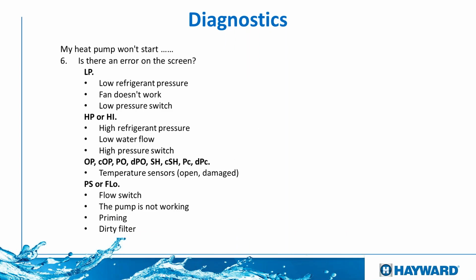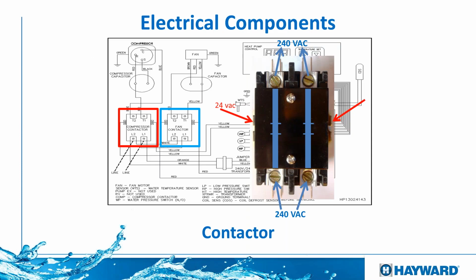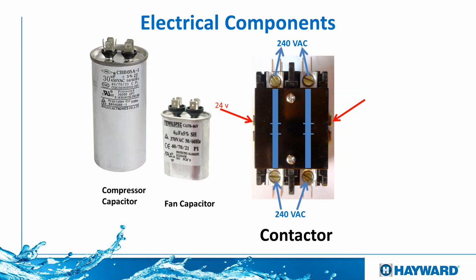Here you see the rest of the codes, but I'm going to break it down into pictures. So first of all, again, you have 24 volts coming in. You have a contactor that's got 24 volts on the coil that closes the contactor and sends 240 volts out to the compressor and starts the unit.